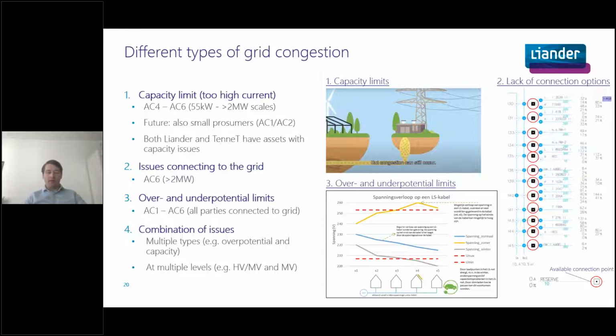Then there's a second type: issues connecting physically to the grid. This only applies to the largest consumers, who have their own connection to the grid. In many of our substations, all the available plugs are already taken, so it's not physically possible to connect. Increasing the number of plugs at such a station can take several years.